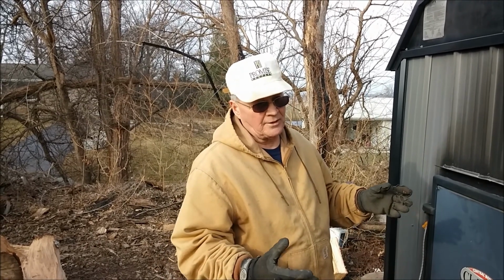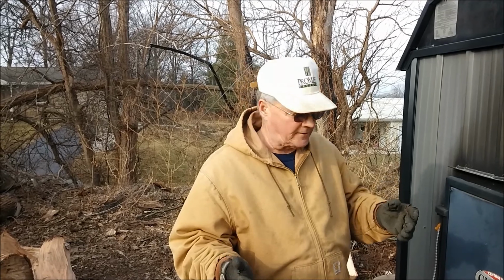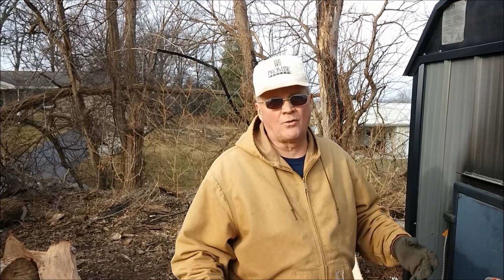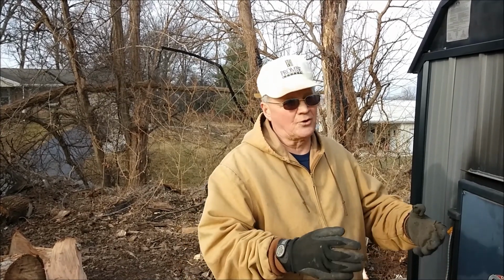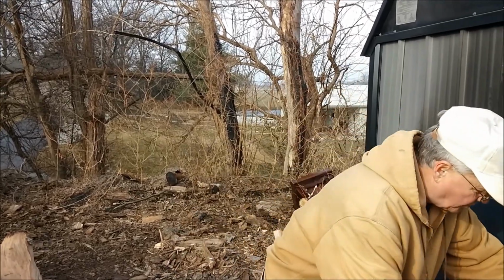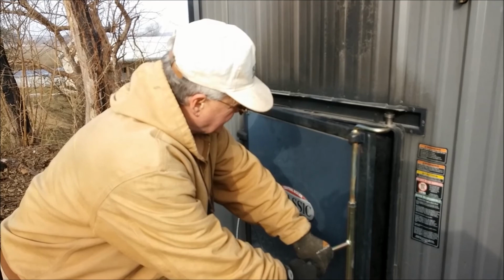And so when the thermostat here says that the water is less than 150, usually about 135 to 140, it'll open up those vents and air will begin to go. And it may take an hour or two before it really gets going. But everything about the whole system happens slowly. It heats up slowly, it cools down slowly, and wood in here, normally we just load it once a day in the morning. Now Wayne's already loaded this, and we'll see what it looks like. It's smoky right now. Yeah, give it a chance to draw some of that up.